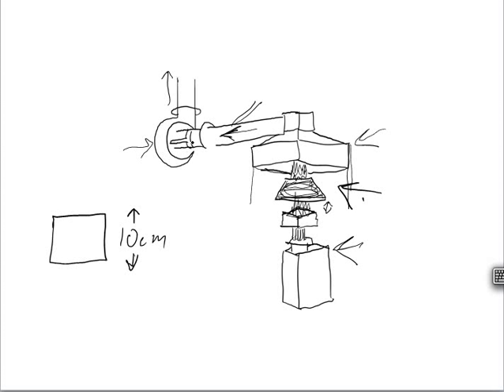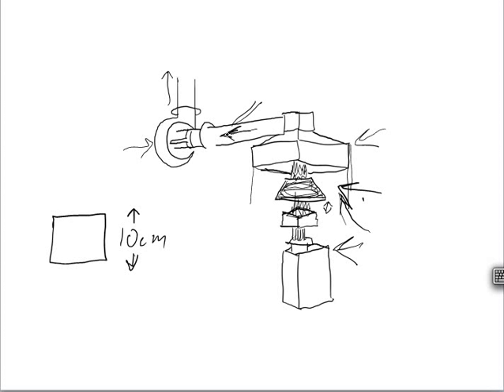If you don't want to, the standard cone calorimeter uses a pump. You can also use this theory. You either want to know how much air is being pulled up through the exhaust duct, or how much air you're pushing past the sample. If you know how much air is coming in, or you know how much air is going out, you can do the analysis either way.